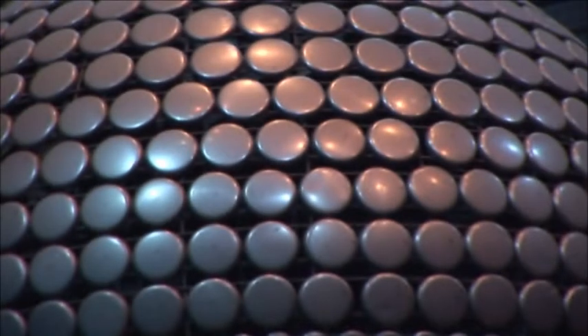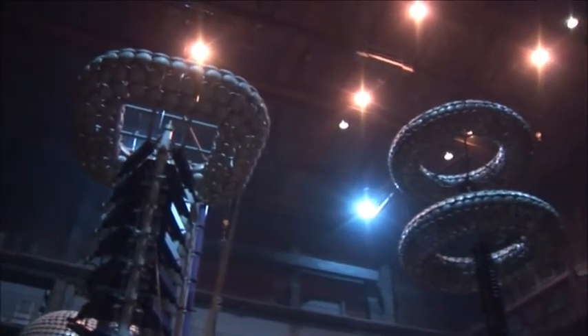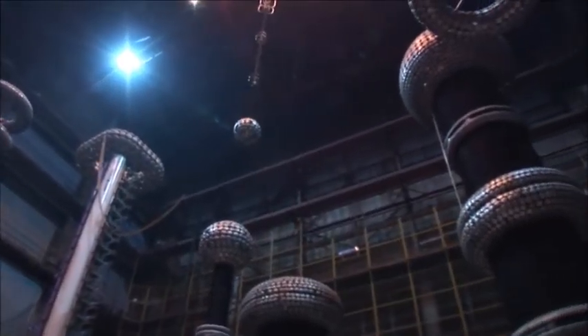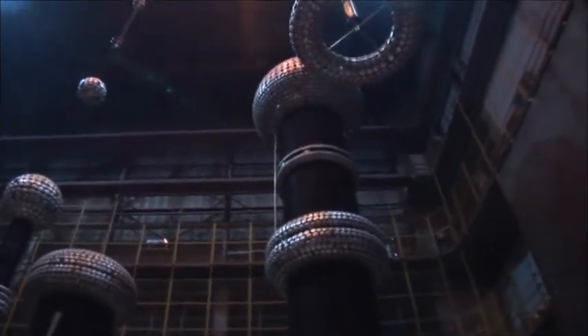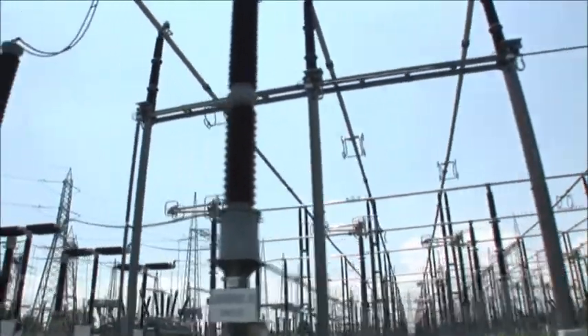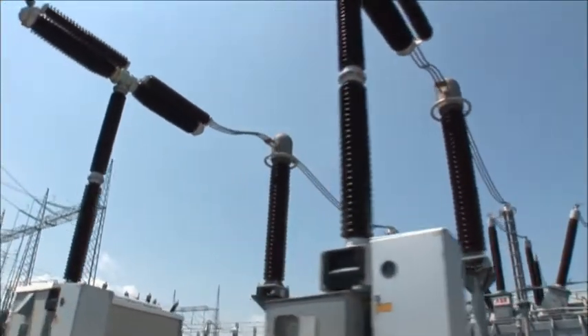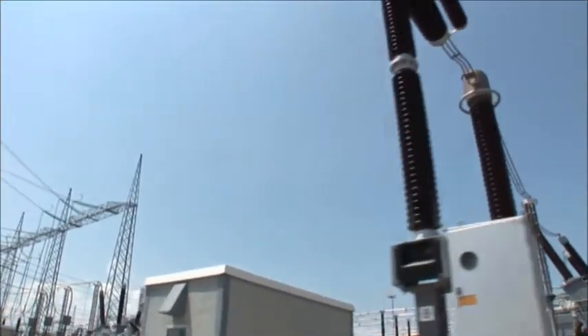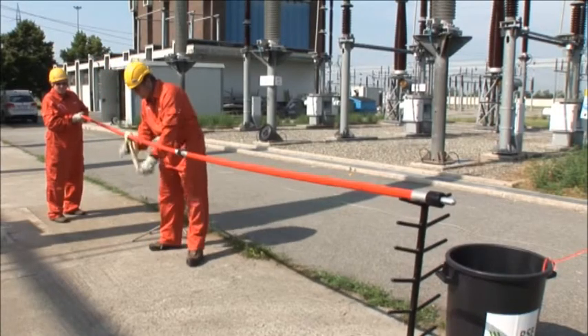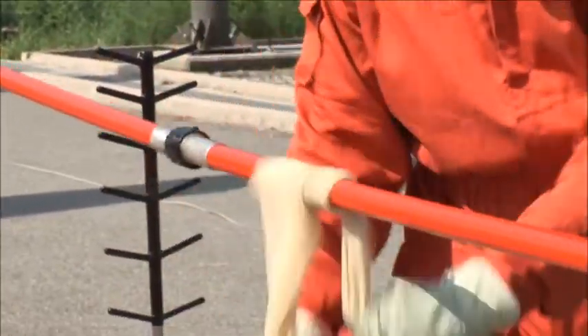The measurements obtained by the voltage and current transformers are compared with those obtained from transportable reference measuring systems, the accuracy of which is kept constantly under control in S.p.A laboratories. The new equipment allows for the connection of the reference measuring systems to the high voltage network without the need to interfere with that already in place. The live line working methods allow authorized personnel to operate safely on live power lines. The current reference measuring system can be installed directly on the live line.